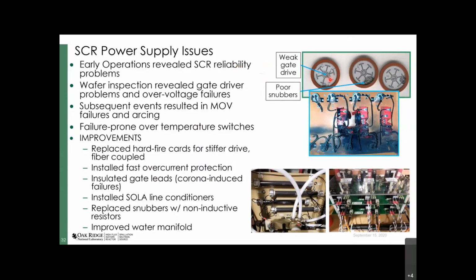Failure near the gate structure tends to be indicative of insufficient gating, because you get very high localized current densities, and you can actually burn holes through the wafer, and that's indeed what happened. The damage you see around the periphery or the edge of the wafer tends to be associated with overvoltage events, where it'll actually flash around the edge and cause it to break down. And that typically tends to be associated with poor snubber design.